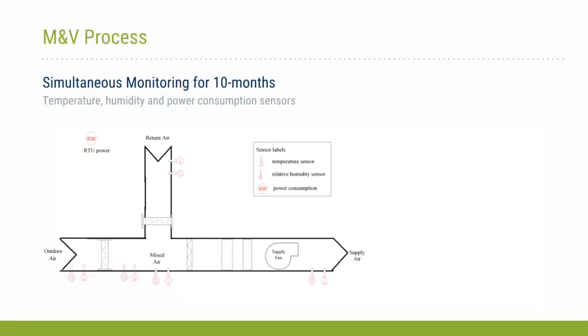So the measurement that we did, over a 10-month period, involved simultaneous monitoring of an existing standard unit and the high-performance unit that was shown previously. And then the measurement plan or measurement sensors are shown in the slide here, right? So in addition to the temperature and relative humidity measurements, we also measured the airflow. For the standard unit, which has a constant speed supply fan, we did a one-time characterization of the airflow to measure what the airflow is in the as-installed condition.